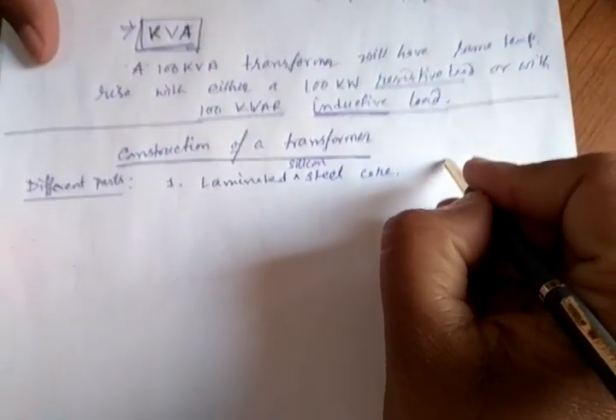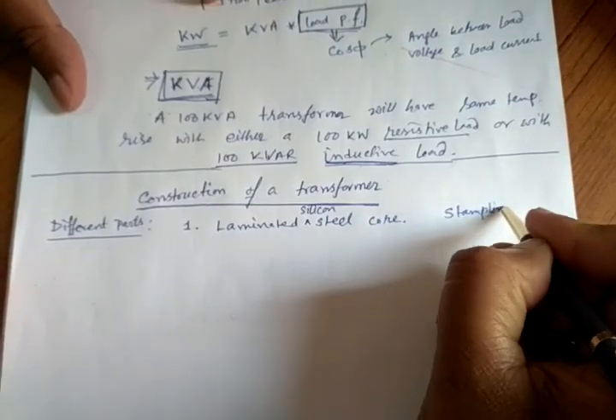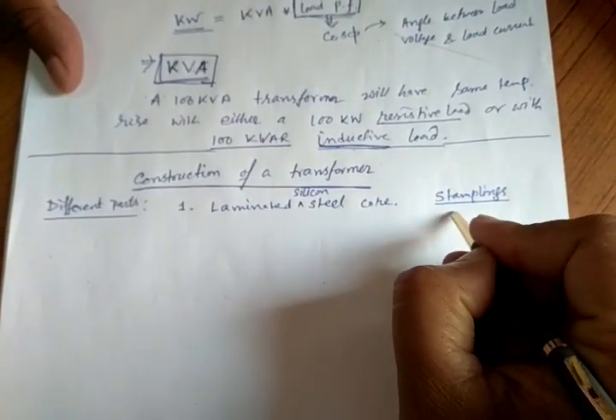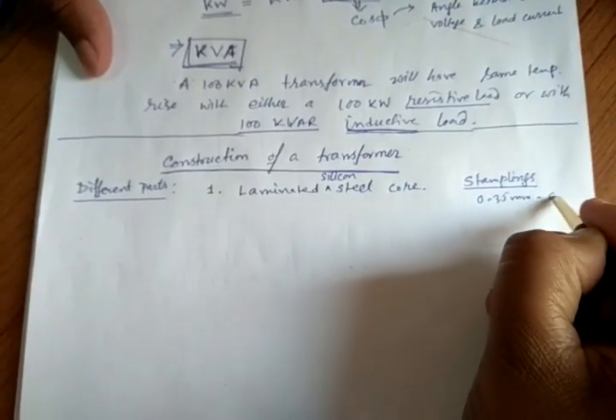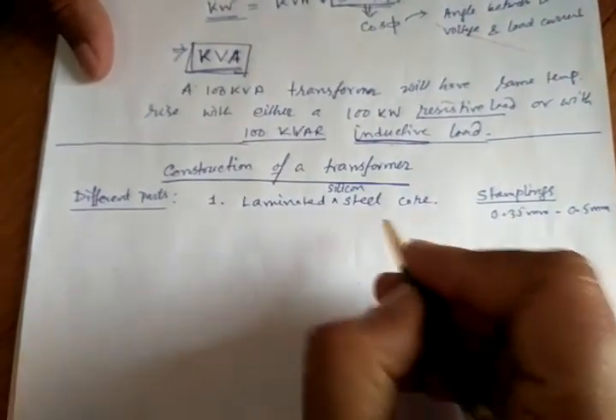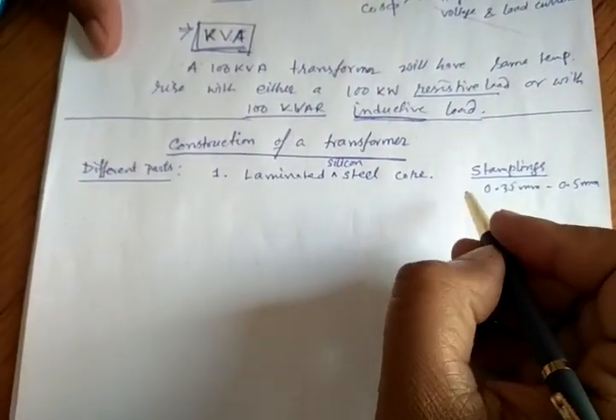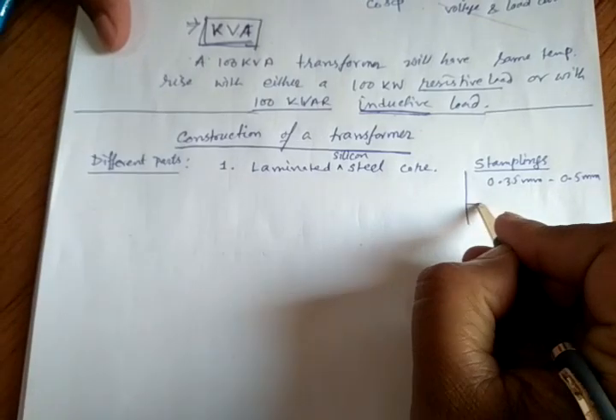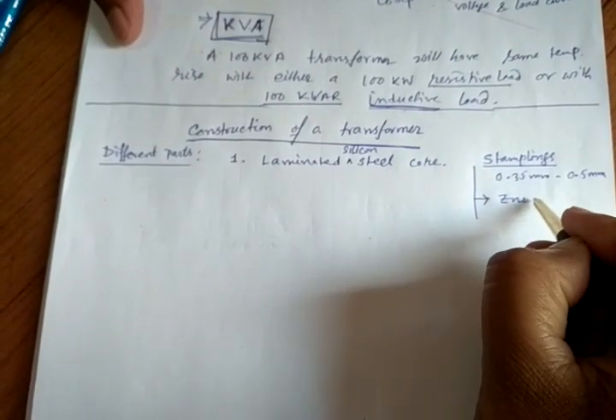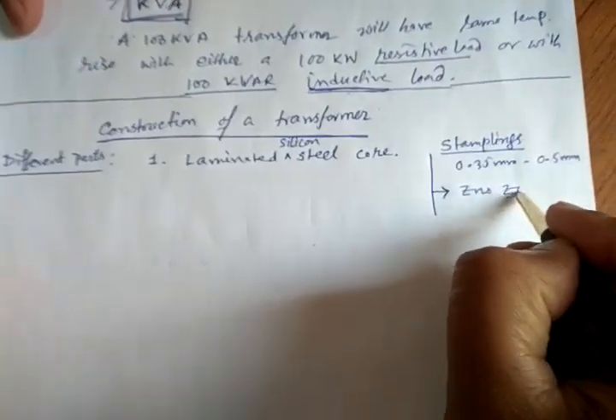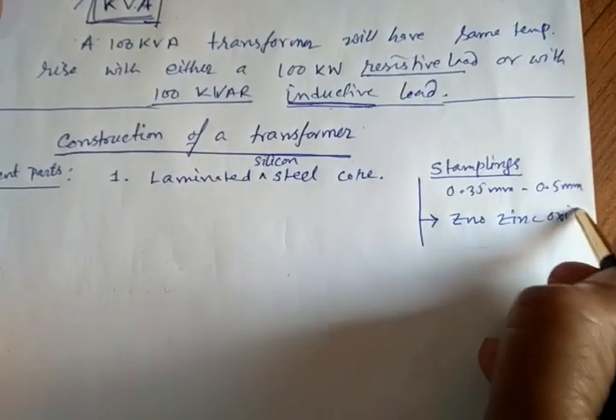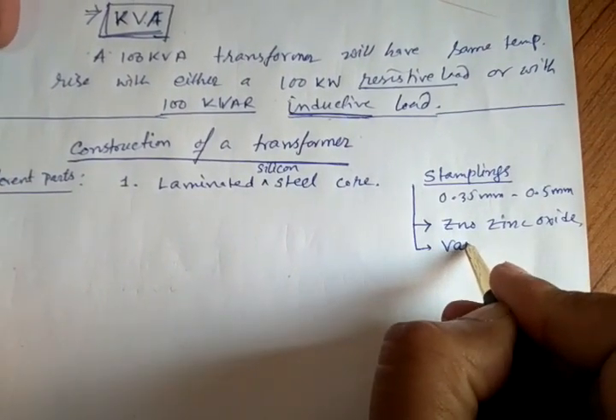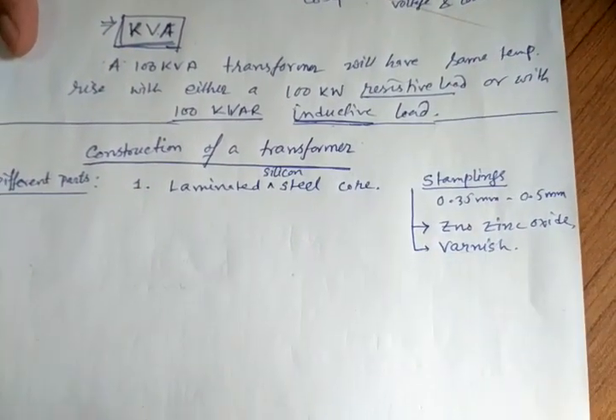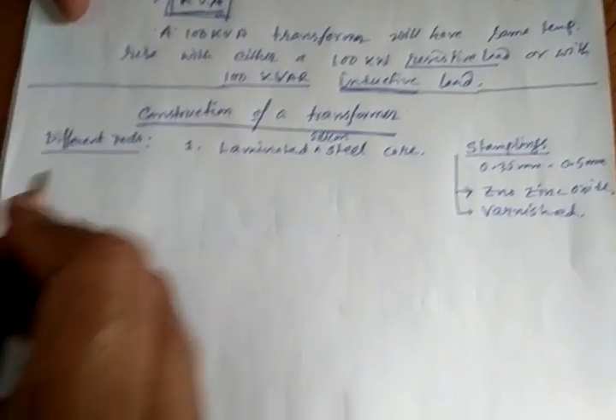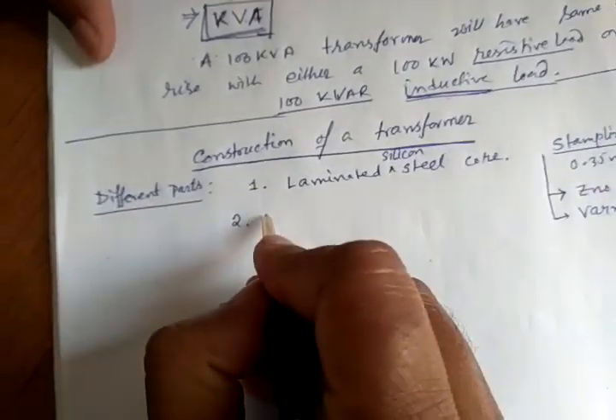So this is, we already know, the transformer core is basically laminated, and each laminated strip size is generally 0.35 millimeter to 0.5 millimeter, and they are laminated. That means they are actually insulated from each other. The insulation is used normally, either they are coated by zinc oxide, ZnO, or it may be used varnished. It is varnished.